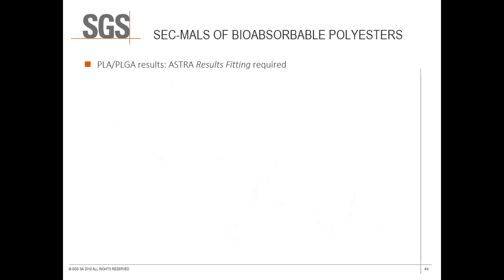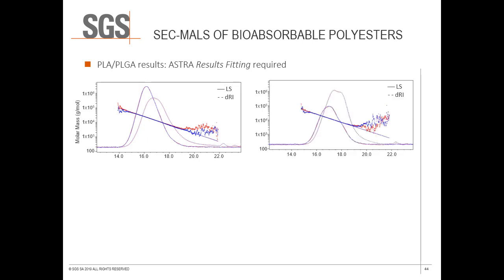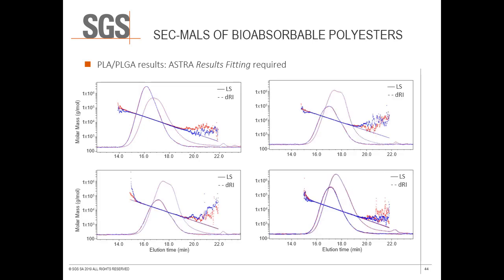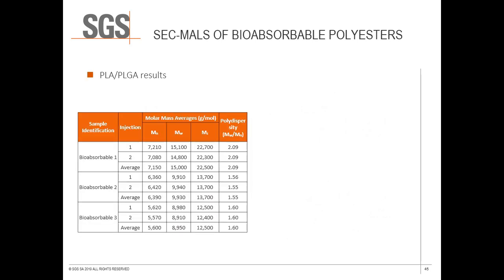The results fitting procedure was applied consistently across all experiment injections, as shown in this sampling of chromatograms and molar mass plots. Note that the bottom right figure actually contains 4 separate injections, duplicate injections of a sample preparation at the beginning of the batch, and duplicate injections of the same sample preparation at the end of the batch, as a measure of instrument and analytical consistency. The non-Gaussian peak shape here is not due to viscous fingering as evidenced by the reproducibility between replicate injections, but is representative of the polymer chain size distribution. The numerical results confirmed the information we had been given regarding the molar mass range of the samples.